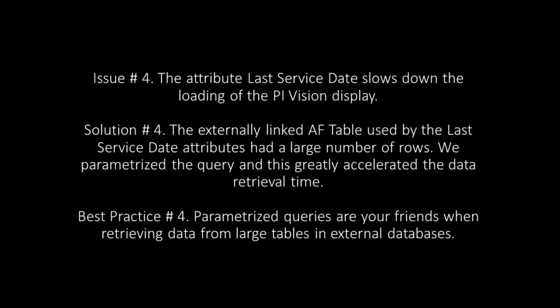Issue number 4 was that the attribute last service date slowed down the loading of PI Vision. Initially, it took a long time to add to the display, and if you did the lab over multiple days, you would have seen that whenever you loaded up the display, it took a long time to populate data. This was extremely evident in PI System Explorer, where it often took a long time to retrieve the data reference values. Doing our research exposed that there was an externally linked AF table, and it had a huge amount of rows. 300,000 rows is unrealistic for a system this small, but on some sites we do see people bringing in tables of that size.